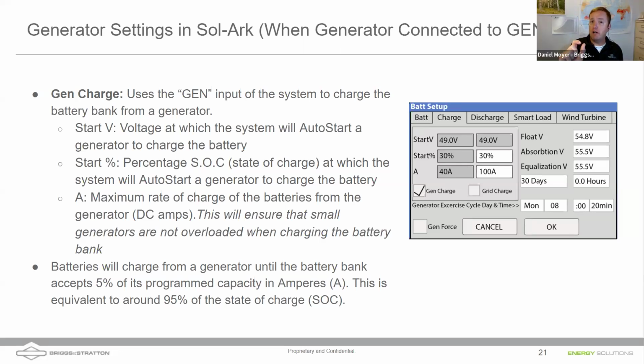So you're either going to use a voltage based setting, and you could find the corresponding state of charge to voltage in our manuals for any battery, I would assume, I would hope. But you could also use a percent charge, and that's going to be dictated by how you're using the Sol-Ark. Another important one is the maximum rate of charge of the batteries from the generator, right? So you don't want to overload a generator that may be on that generator port. So what we're telling the Sol-Ark is when you want the generator to start, at what battery reserve level. And that's where you do this.